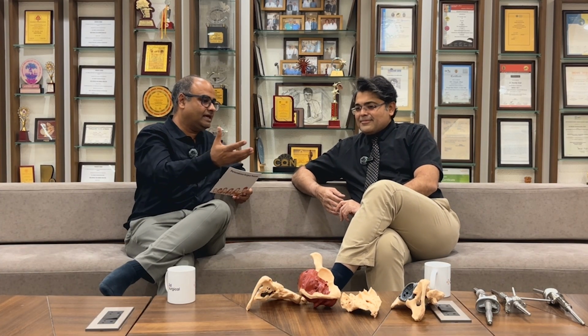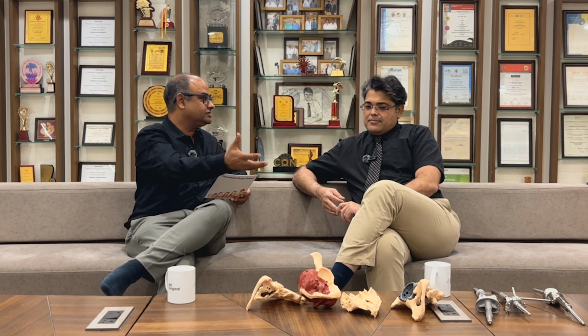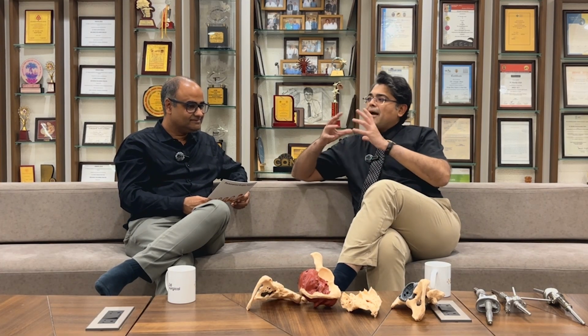Sometimes it helps, like in the hip situations, but there is also personalization in knee situations where you feel, hey, intraoperatively, if I have to have flexibility, personalization is great, but not really, because I want flexibility in the surgery. If there are things that I find out in the OT, then I need to have the flexibility. So you have to have modularity in one area, and a patient specific implant in another area, and you can have a mix and match of both.